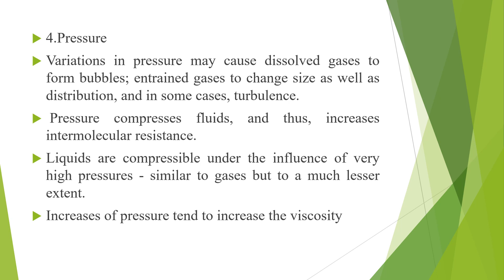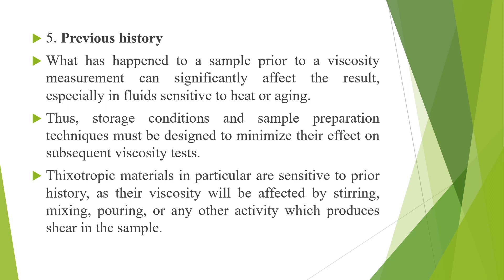Fifth point is the previous history. What happened to a sample prior to a viscosity measurement can significantly affect the result, especially in fluids sensitive to heat or aging. Thus, storage conditions and sample preparation techniques must be designed to minimize their effect on subsequent viscosity tests. Thixotropic materials in particular are sensitive to prior history as their viscosity will be affected by stirring, mixing, etc. or any other activity which produces shear in the sample.